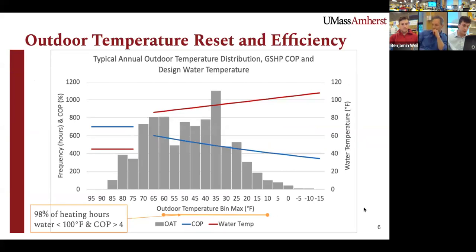And so this slide basically just reiterates what was previously talked about. It shows that as the coefficient of performance, which is the blue line, decreases, the water temperature, the red line, increases. It is also showing that for a majority of the days, the outdoor temperature is around 35 degrees, so the water temperature will not need to rise above 100 degrees very often. In fact, 98% of heating hours will be below 100 degrees Fahrenheit and above a coefficient of performance of 4.